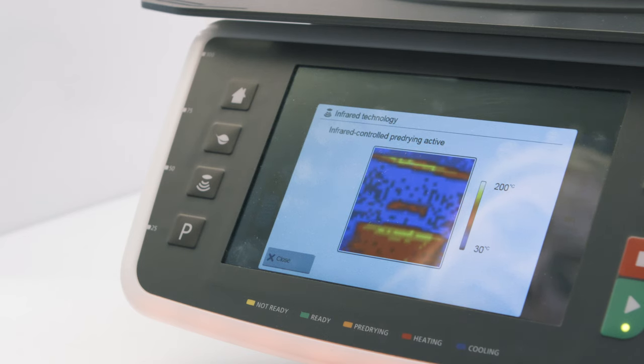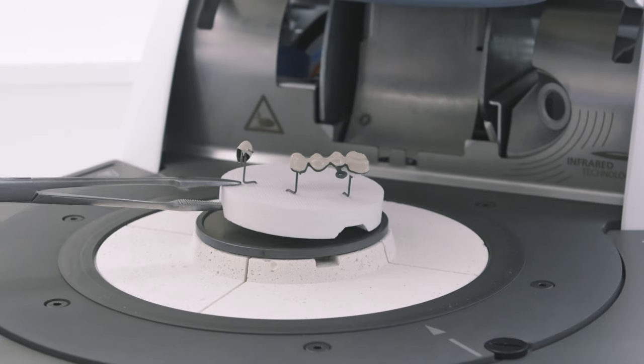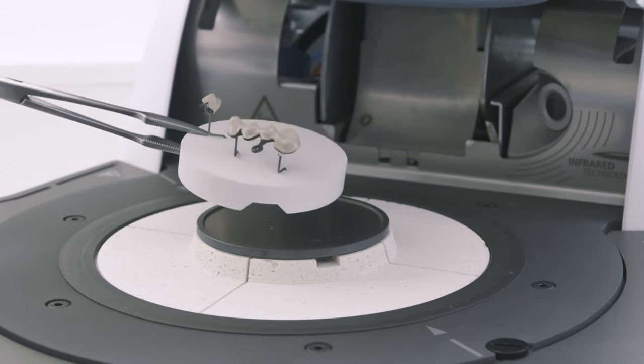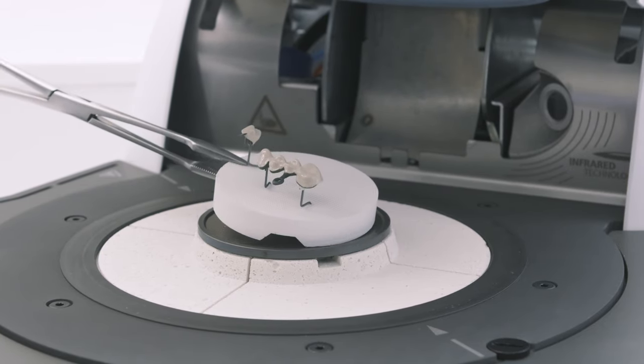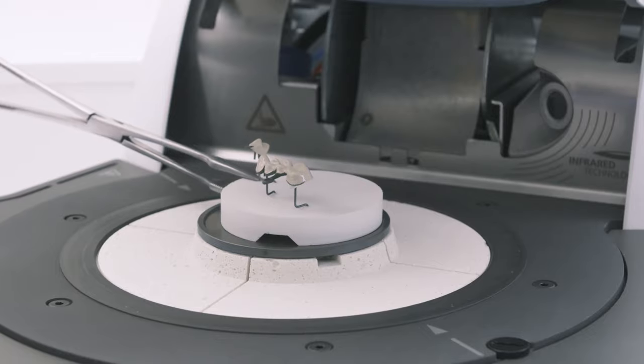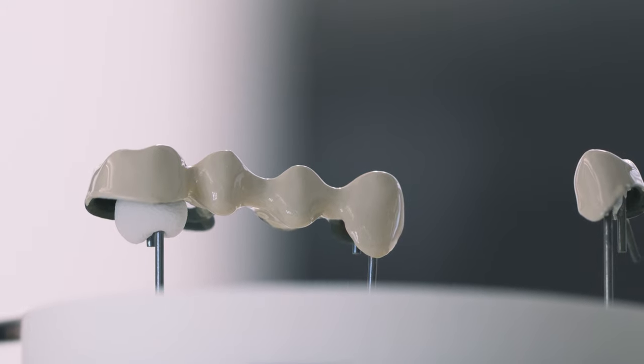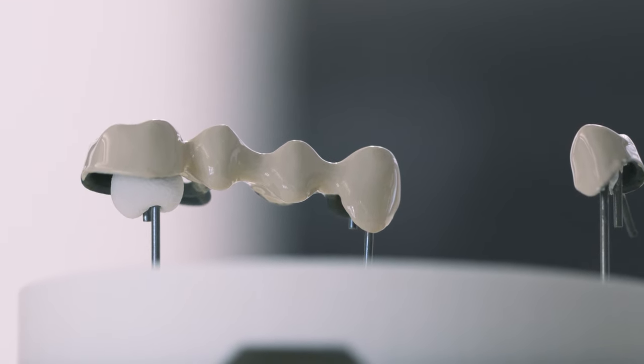The infrared technology is not suitable for measuring the temperature on metal frameworks. Metal frameworks that have been veneered with opaquer or ceramic must be placed in such a way that the metal margin or holding pin is not caught by the camera.